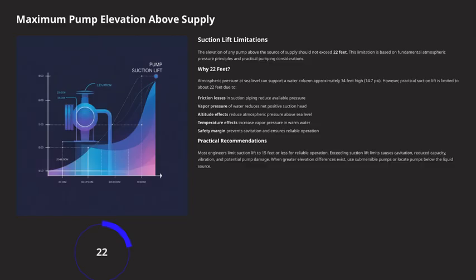This limitation comes from several factors. First, friction losses in the suction piping reduce the pressure available at the pump inlet. Second, the vapor pressure of water, especially in warm conditions, reduces the net positive suction head the pump can handle. Third, altitude effects decrease atmospheric pressure as you go higher above sea level, further limiting lift capacity, and temperature increases vapor pressure, which can lead to vaporization within the pump. All of these factors mean that exceeding this 22-foot limit increases the risk of cavitation, which can cause vibration, reduce pump efficiency, and even lead to damage.